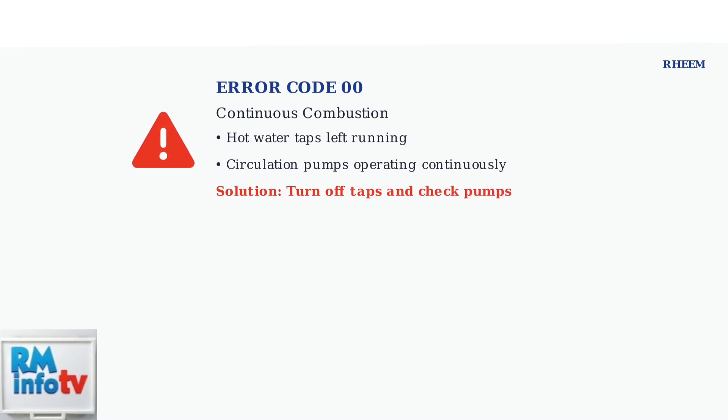Error code 00 indicates continuous combustion for over an hour. This usually happens when hot water taps are left running or circulation pumps operate continuously. Simply turn off the taps and the error should clear.